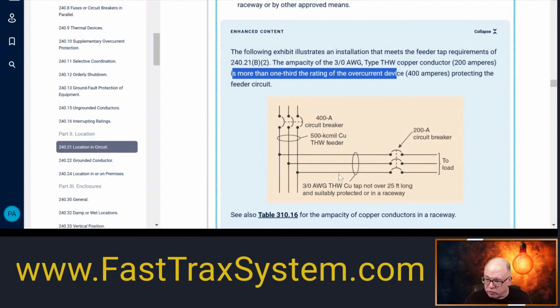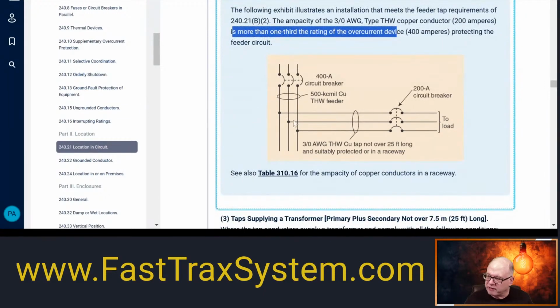This is where the tap rules kick in. And just in this case, it's showing them tapping onto the actual conductor. Okay, but you know what's so funny is they could actually have connected right here, and the same rules would still apply. These conductors right here would be following the not more than 25 feet tap rule. Okay, so don't get locked in your mind that it only has to tap to a conductor, because that's not the case. Okay, all right. So anyway, let's get back to the tap part. So here's the taps. And this portion right here, from here to here, cannot be more than 25 feet.